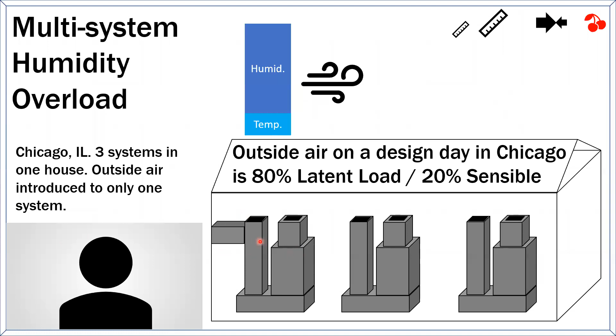This is Chicago, not Austin, but in Chicago, 80% of the load coming in on that outside air is moisture. Only 20% is sensible. You can absolutely overload this thing to the point where it's not able to keep up with the humidity, and the zone that's being served by this unit just becomes humid, because you should spread that outside air out. But technically I meet the code when I do this in my big house, and it's a bad idea.